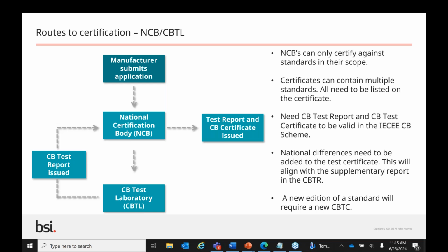NCBs can only issue a test certificate for products within their own IEC scope, and you can find a certification body or a test lab's full scope on the IEC website. For a certificate to be recognised as valid within the CB scheme, you need to have both the report and the certificate when making that submission. And lastly, the CB scheme is not a one-off certification. So when the standard updates, you should also think about updating your test report and certificate to the latest version. Next slide, please.